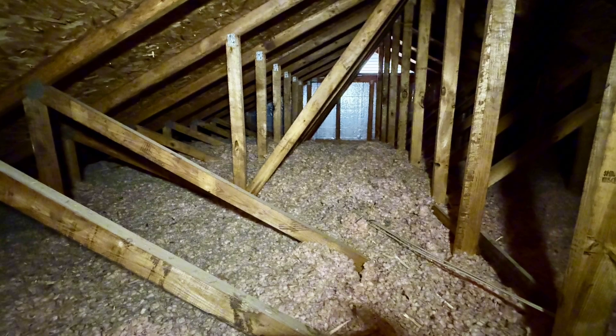That's why the basement basically just stays cold — it just repeats the cycle. It's a relatively simple fix that would have been very easy to address when the house was originally built, but now because of drywall installed in the basement and ductwork underneath, you would have to remove drywall to fix this properly. I think it's worth it, because the only real alternative is installing a second heating and cooling system in the attic. Open up the drywall in the basement, reconnect the return trunk line into the wall cavities, and you'll be pulling a lot more air down from the second floor.